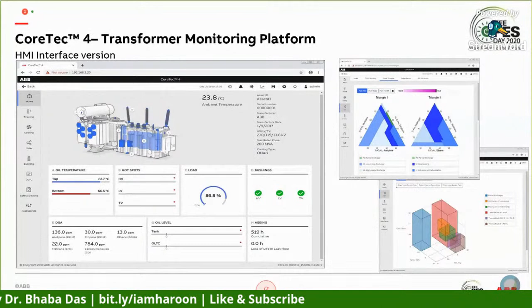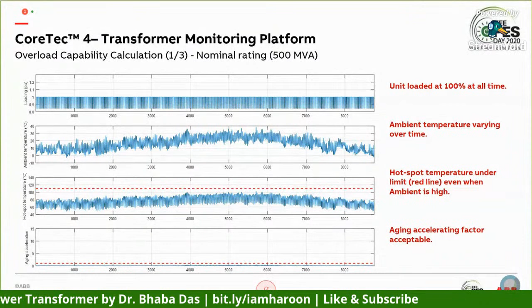Then we migrate to the fleet level. So what is the CoreTec 4? What are its capabilities? I'll give you an example. We have always had questions from people about, can I load my transformer at 100% when my ambient temperature is high. So with the CoreTec 4, now for every single day, for every single hour, you will have the hotspot temperature calculated. If you look at this diagram, our hotspot temperature is always below the maximum acceptable temperature for the entire duration of the time. That means even though you are loading the transformer at 100%, you are well below the margin and your accelerated aging factor is acceptable. So the question, can I load my transformer to 100%, is answered.